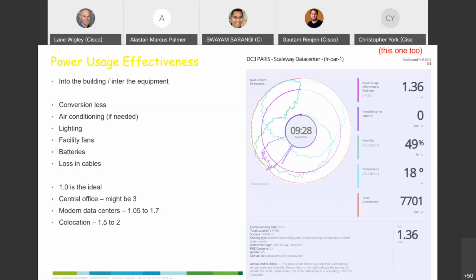Different environments will also have different types of air containment. If you go into a building built back in the 40s, it's not necessarily going to have hot aisle, cold aisle—it might have some very rough containment that looks like shower curtains. So PUE can range from just over 1 for an absolutely modern data center up to something like 3. I wouldn't be surprised if a lab was in that 3 or higher range. Every watt we save in this case would be 1.36 watts for this customer, but for a lot of our traditional telco customers, it's much higher.